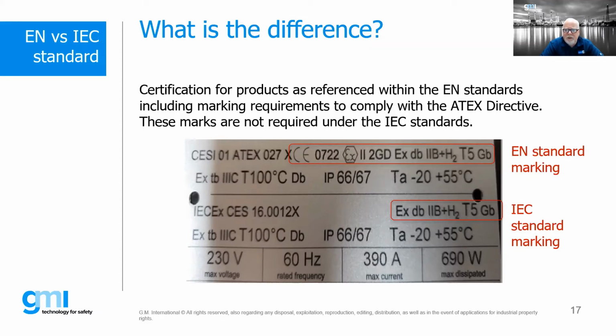And then we don't see things like a CE, the 0722, the EX, the Roman numeral II, 2GD, and so on, but we find the other information. So it's left up to the manufacturer on exactly how they wish to mark products if they have both ATEX and IEC EX, but there are details in the -0 standard that give that information on exactly how manufacturers should be marking products.